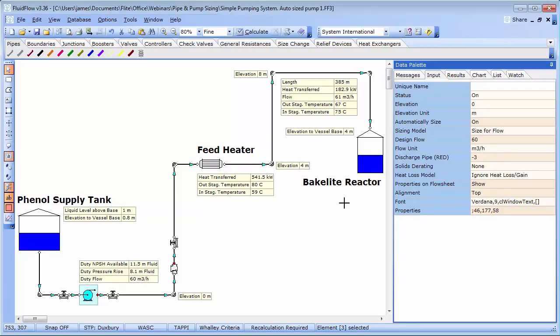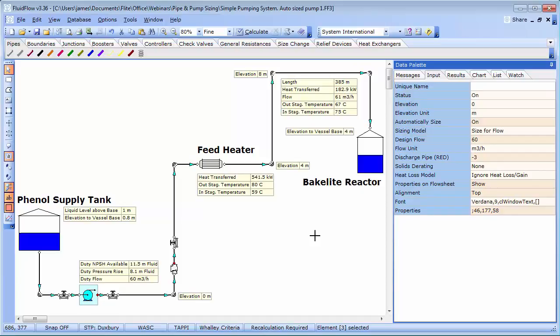Often a good starting point is to size the pipework using economic design criteria and for anyone interested we have a really useful article on our website under the resources section which discusses this topic of economic pipe sizing. In essence, economic design criteria considers maintenance costs, energy costs, installation costs, operating frequency of the system etc. and these parameters are different for different pipe materials.